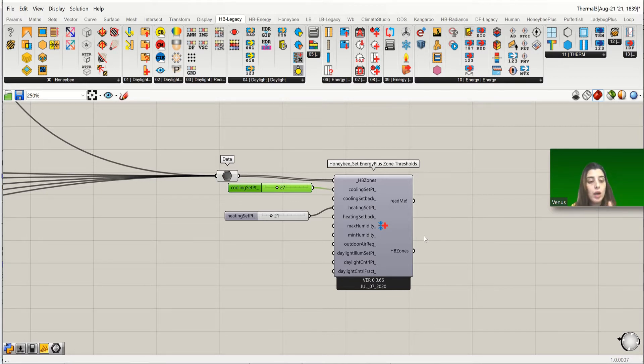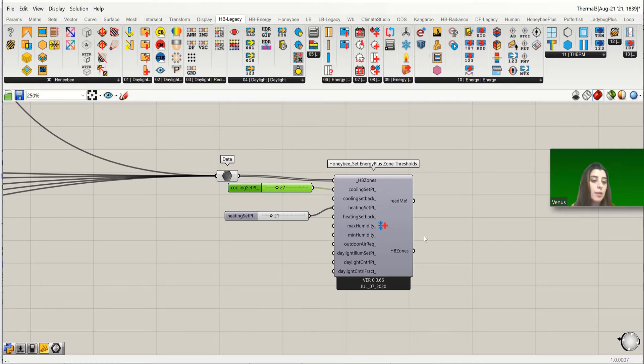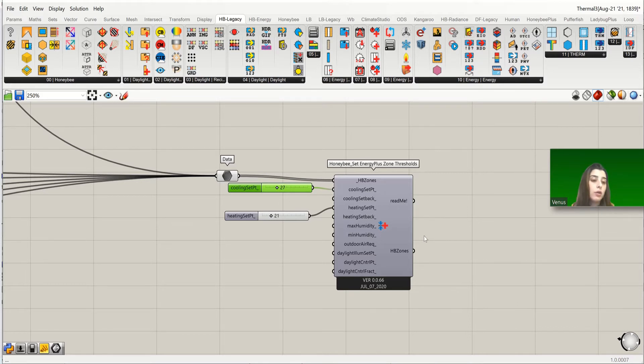We need to define cooling set back and heating set back for our system to control zone temperatures while the building is empty. This is especially useful for office and commercial buildings, because it helps the HVAC system manage conditions efficiently and can reduce and save energy. If the HVAC system only starts working right at 7 a.m., it puts excessive pressure on the system, increasing maintenance needs and costs.